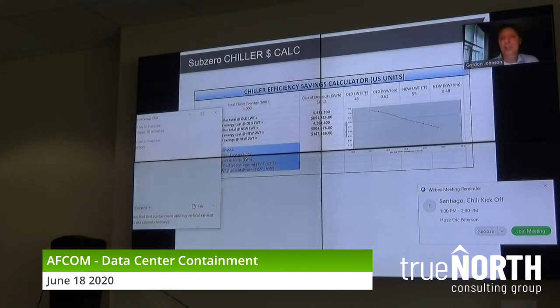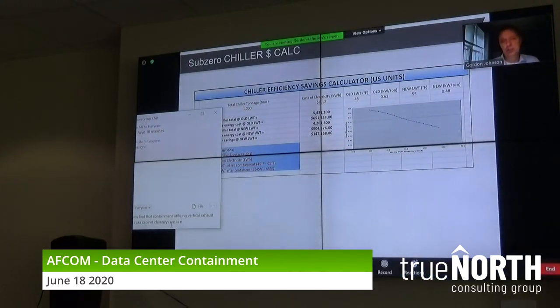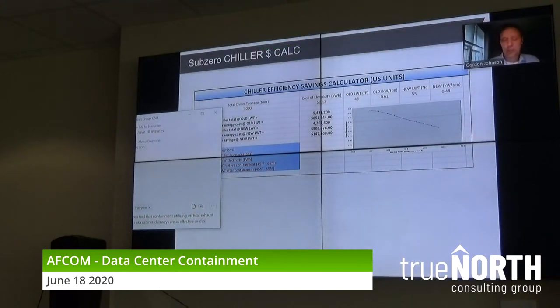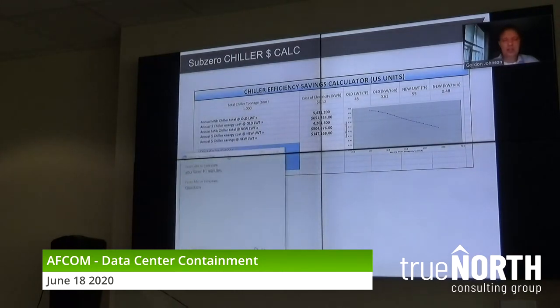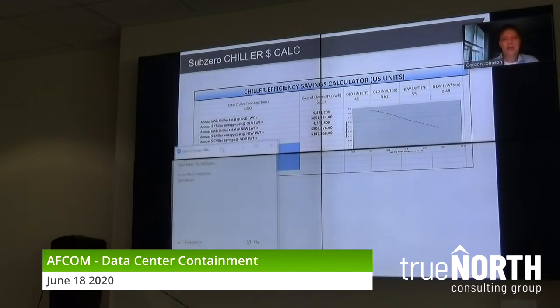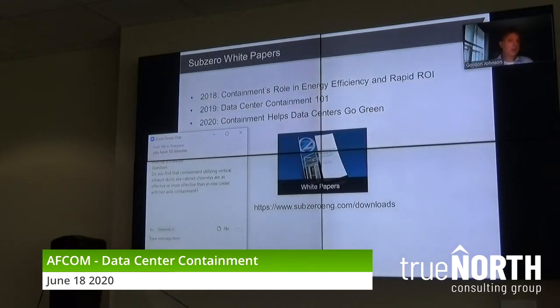I just added the chiller efficiency calculator. You add your tonnage, your electricity, your leaving water temperature, your new leaving water temperature after installing containment. It will tell you how much you're going to save. I even touched real briefly on the CFM per pod, depending on heat load. I've really automated that process in one of these calculators, but also left in a manual way to do it. Like I said, if it's something of interest to you, please go to our website and download it.